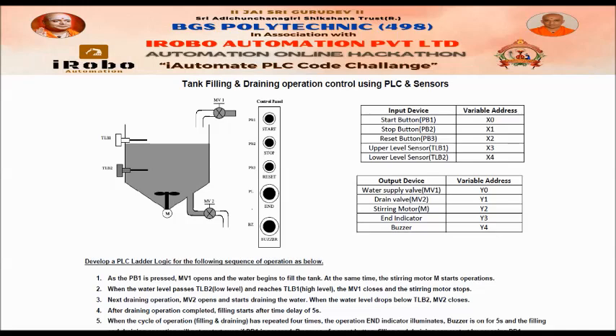When the start button is pressed, both valve MV1 opens and the stirring motor turns on simultaneously. When the water level reaches the low level, filling continues. When it reaches the high level, MV1 closes — meaning filling is stopped — and the stirring motor also stops.